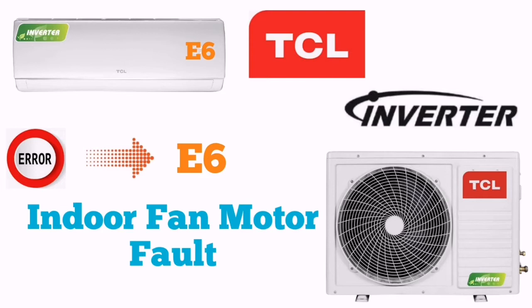And again, if you are getting the same error, then you have to check your fan motor and you have to replace the fan motor. Your indoor fan motor will be working.